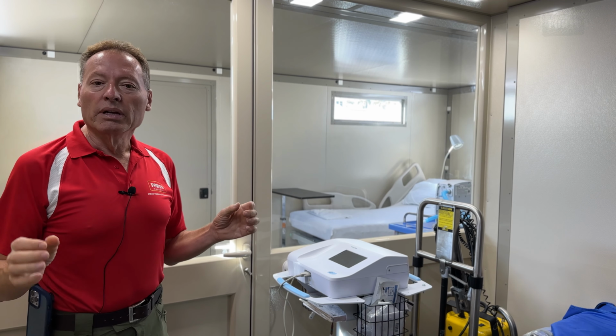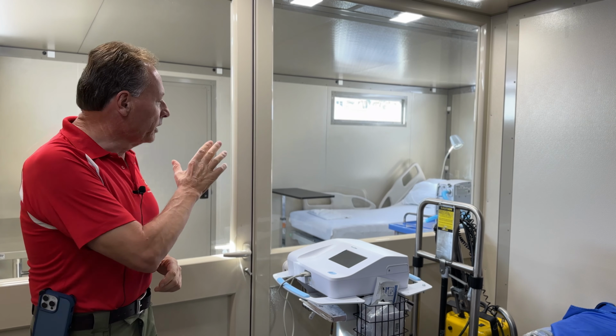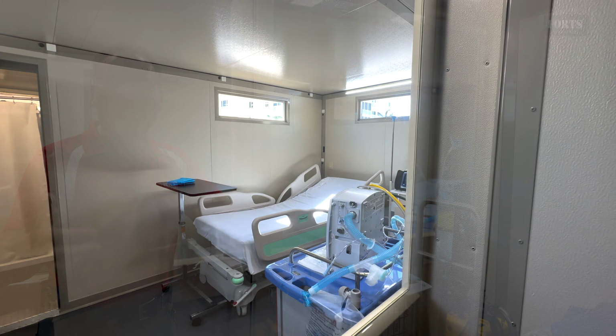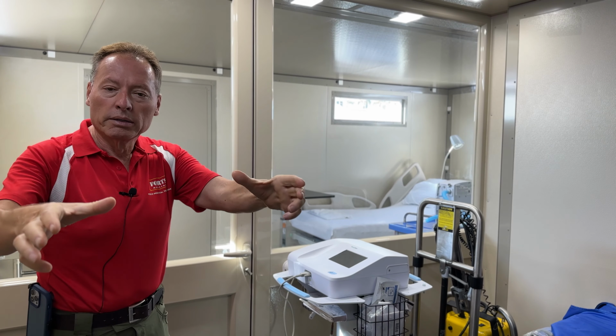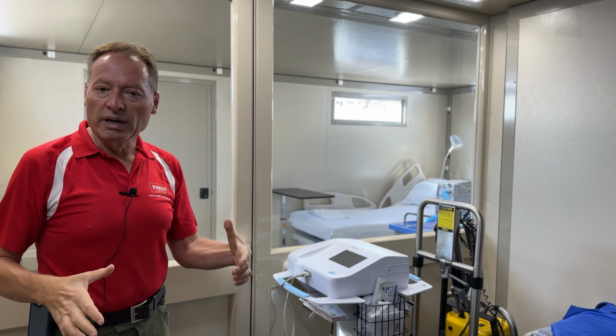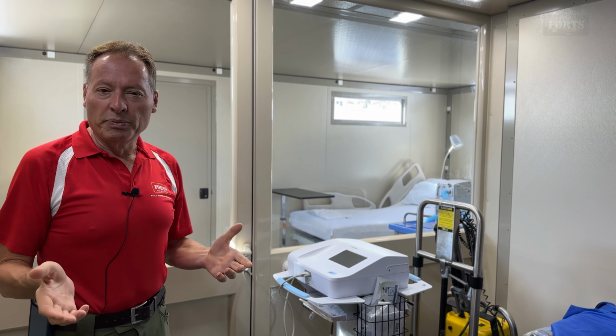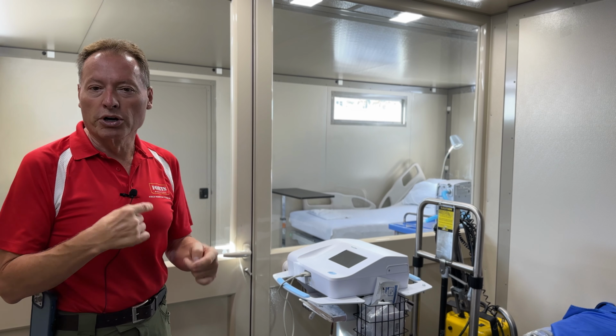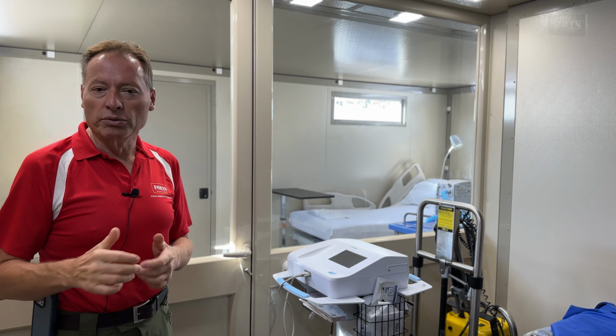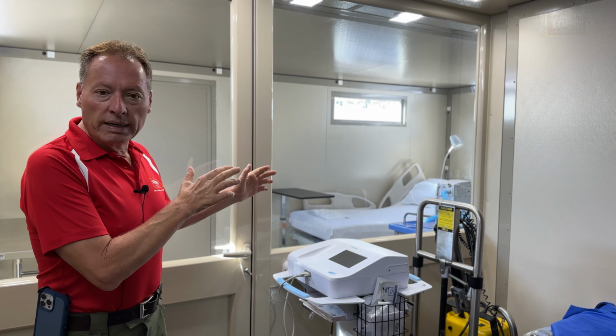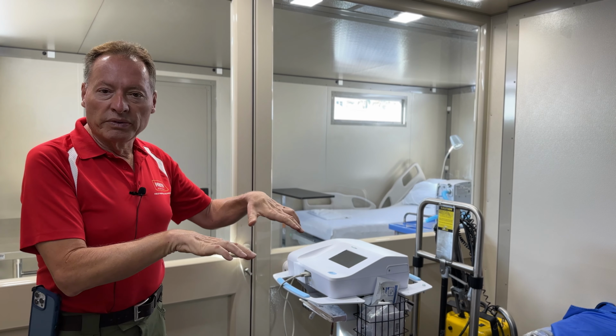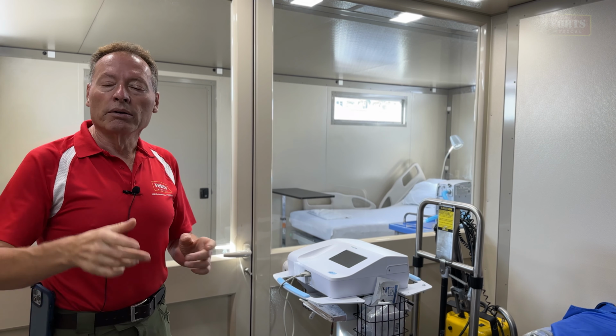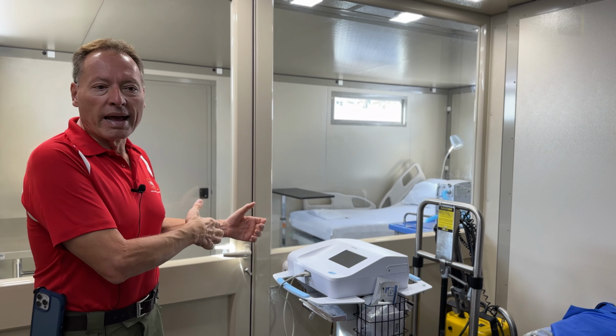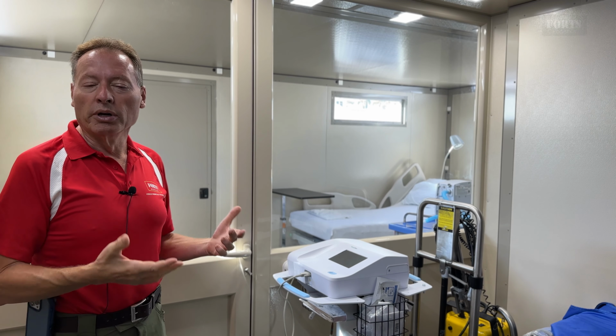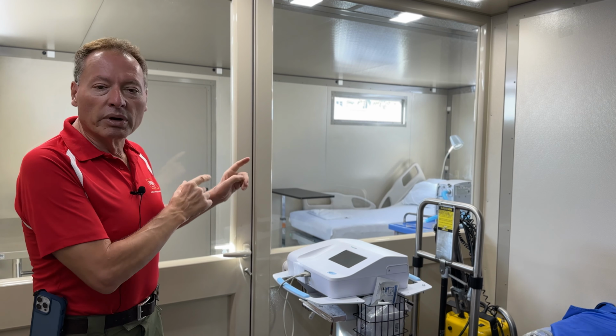We are now situated in the clean anteroom right before entering the isolation room. This is located at the end of the hospital, so we had the emergency ward, the procedure room, and now we're in isolation. Here in Fort Myers Beach, we've used extensively the isolation room for our COVID cases before retransferring them to Ultimate Care. This is totally negative pressure inside the room, positive in here, and we will see that that is fed from a trailer unit outside that pumps in fresh filtered air and aspirates the dirty air that is soiled with contaminants. Now let's go inside the room.